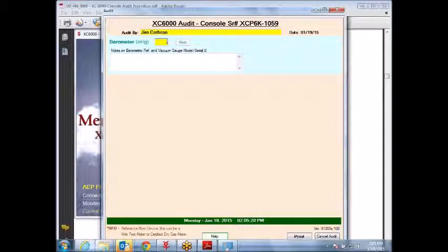So, I've got a Mercury barometer here in our Cal lab, and that's where I got my numbers from that I'm using here. Okay. So you put in baro. Again, a lot of this is tracking type information, whatever you really want to put.